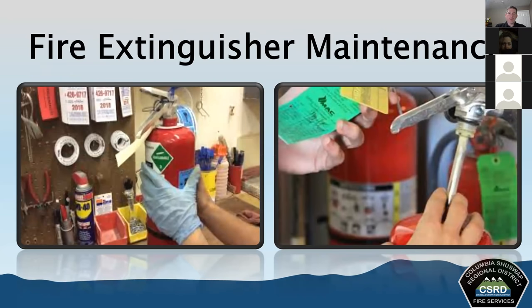For maintenance, extinguishers should be taken out of service annually for a thorough inspection and disassembly. Any pressurized extinguishers must also be hydrostatically tested as required by Transport Canada, and test results should be affixed to the shell. Dry chemical extinguishers should have their agent emptied and replaced every six years, done in a controlled atmosphere by qualified personnel — in our case, by external contractors.